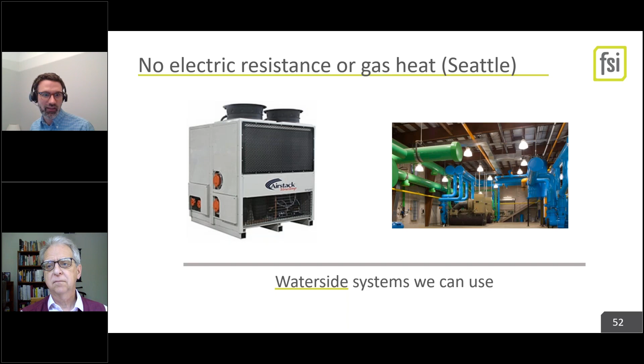Hit the next slide. This is the big aha: your boiler over here on the right, this is from a life science project that we are just getting done with design in Seattle. We were not allowed to use boilers or much electric resistance, nor did we have the electric service to do it. The heat recovery chiller, to make an air to water heat pump, same thing, to make the same capacity as a boiler. You can see the size comparison now: 4,000 pounds, about 8 feet long, versus 17,500 pounds, and 43 and some feet long. So there is a size, electrical, structural, keep going, impact to making these choices.